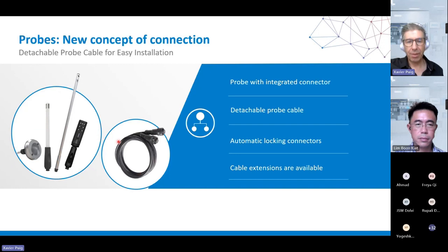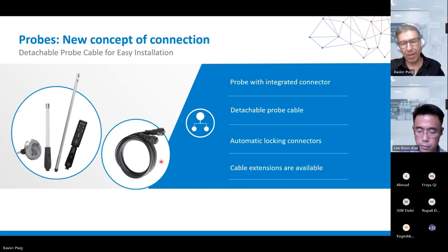On top of this cable, we have two extension cables, one being 5 meters and the other 10 meters in length. So in total, you can add the normal probe cable, which is 2 meters, plus 15 meters of extension, up to 17 meters. It's perfectly fine. And like before, now all the probes can work with this distance without any issue. I really tested it myself, so it's working perfectly fine for the new probes. So remember, the probe cable is always needed, plus optional cable extensions of 5 and 10 meters. We can combine those two, plus the probe cable, to make 17 meters maximum.